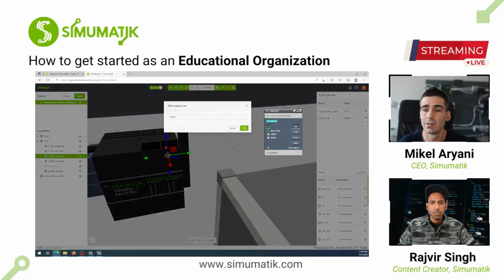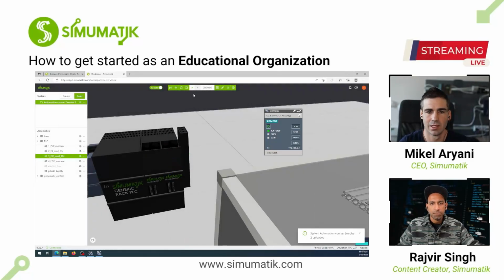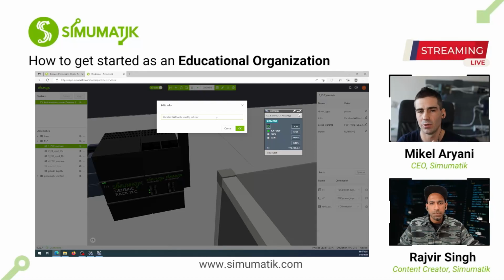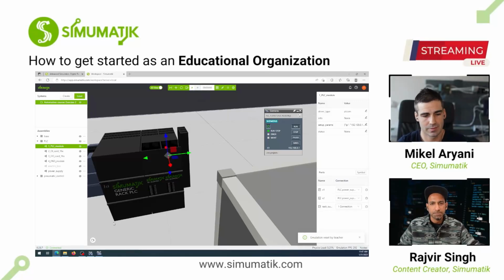So let's say we are going to read from QW0. Now the model is actually ready. Let's try again. We click play. We will get this error: write quality error. This is because the PLC is not set up for allowing communication, for reading IW0.